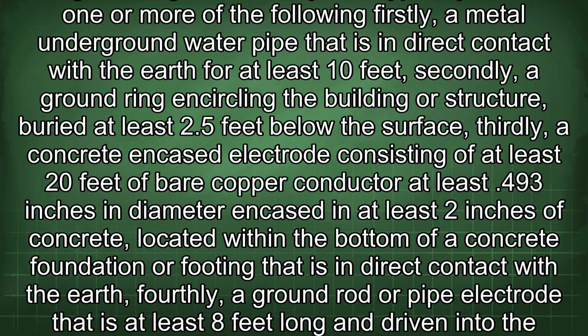The grounding electrode system typically includes one or more of the following: firstly, a metal underground water pipe that is in direct contact with the earth for at least 10 feet. Secondly, a ground ring encircling the building or structure, buried at least 2.5 feet below the surface. Thirdly, a concrete encased electrode consisting of at least 20 feet of bare copper conductor, at least .493 inches in diameter, encased in at least 2 inches of concrete, located within the bottom of a concrete foundation or footing that is in direct contact with the earth. Fourthly, a ground rod or pipe electrode that is at least 8 feet long and driven into the earth. And fifthly, other listed grounding electrodes.